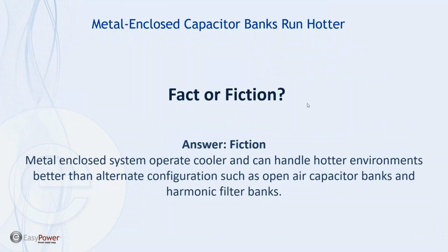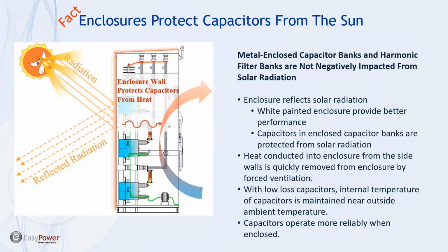no limits in size. There's a notion that metal enclosed systems run hotter, and people would think about their car. When they get into their car in the summertime, they say, "Wow, it's hot," and therefore they think a metal enclosed filter bank would be hot, or a metal enclosed capacitor bank would be hot, because they compare what they feel when they hop into a car versus what an enclosure would have. So they have a feeling that it runs hotter. But the reality is that in a metal enclosed system, the skin of the enclosure reflects the sun away from the equipment.